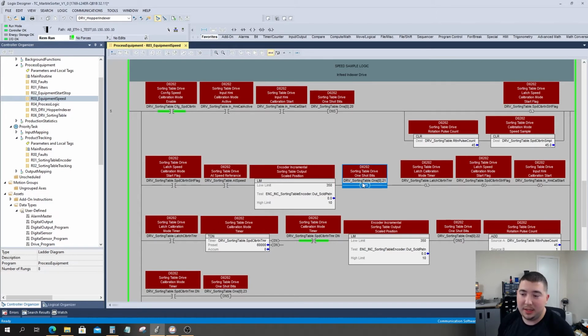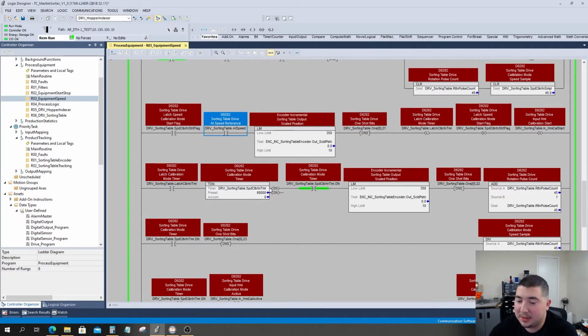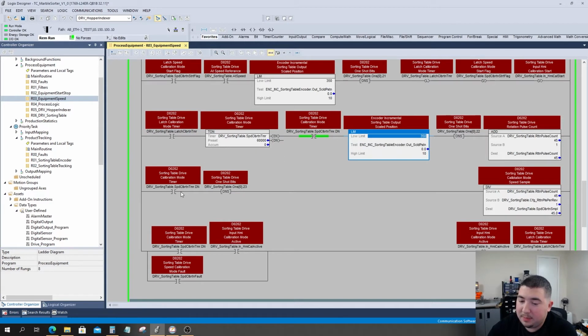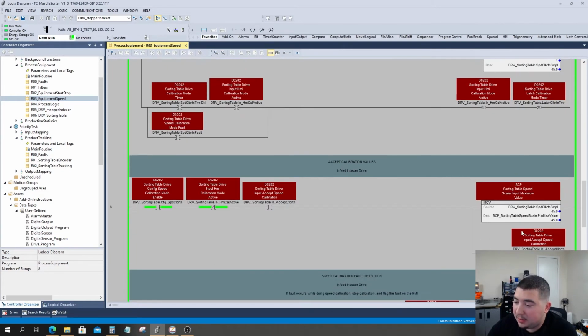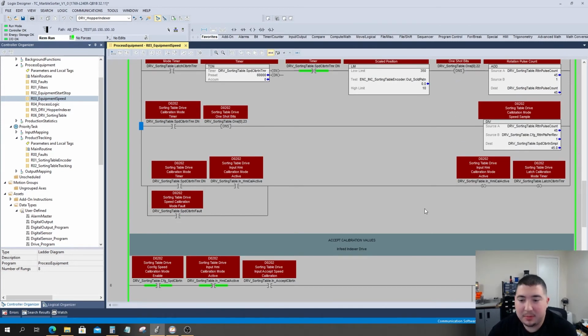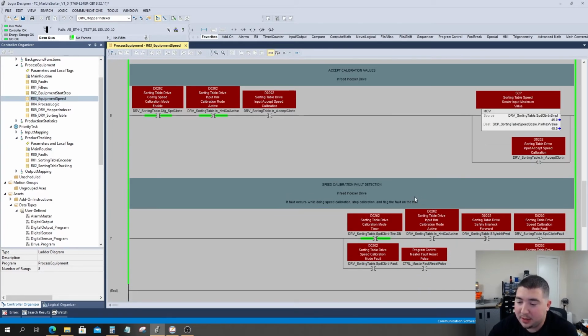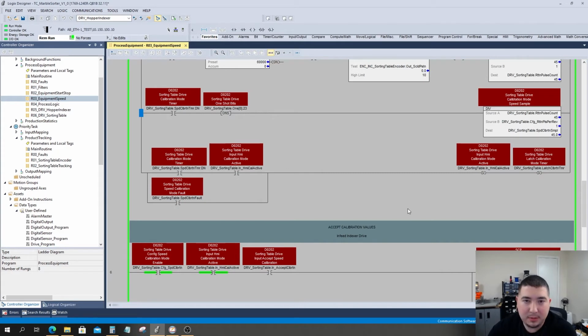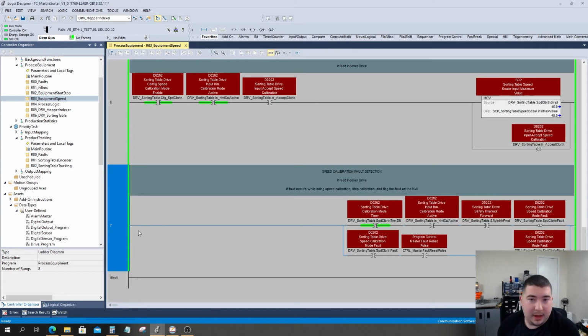Once it's actually in position and at speed, we'll then latch the timer, and every time the encoder comes back to this position, we will increment our counter. When our counter is complete and we've finished counting for that minute, we will store our value in our speed sample tag. Since there's only one time that we'll reach this position in the full rotation, we still do the divide, but we just do it once, so it's just divide by 1, and then our output can be stored into our final value for the maximum scale set point. Again, we also have a fail-safe. In the event that the motor fails while we're trying to do the speed sample, we will stop and we will issue an alarm.